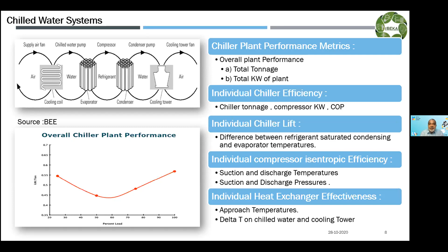So in case of chiller, you will find at 60% loading or 50 to 60% loading, the kilowatt per ton is very less. So we are required to focus the overall plant performance by parametric optimization, by adaptive approach, so that for every loading condition, my plant is going to deliver the expected energy efficiency. So in chilled water also, we are having a lot of opportunity for no or low investment cost saving.